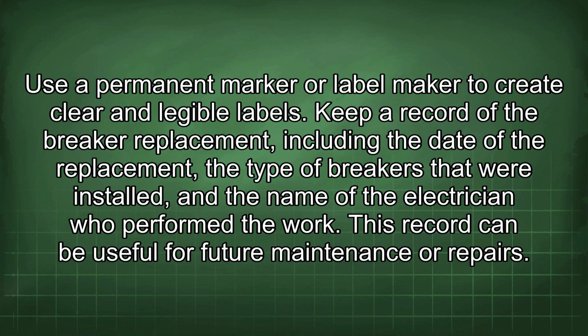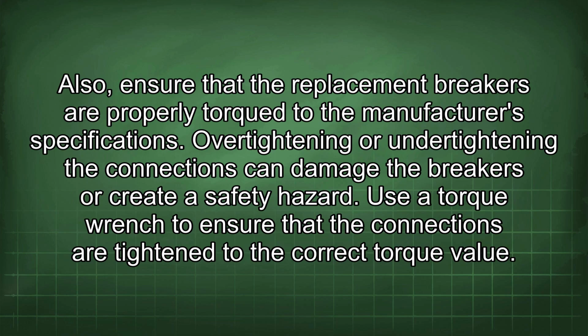This record can be useful for future maintenance or repairs. Also, ensure that the replacement breakers are properly torqued to the manufacturer's specifications. Over-tightening or under-tightening the connections can damage the breakers or create a safety hazard. Use a torque wrench to ensure that the connections are tightened to the correct torque value.